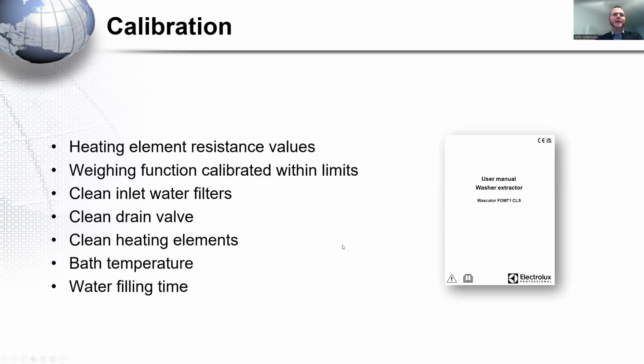So to the internal vital conditions that can be calibrated in this machine, we have the heating element resistance values. And the resistance of the element, of course, is giving you the heating power of the machine together with the voltage. So there should be the correct voltage marking on the heating elements, and they should be within the resistance values given for that voltage.